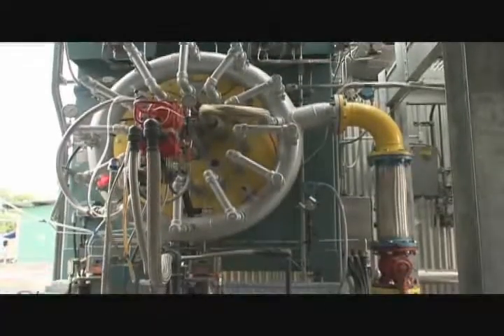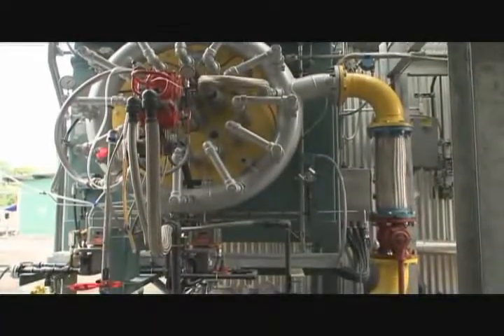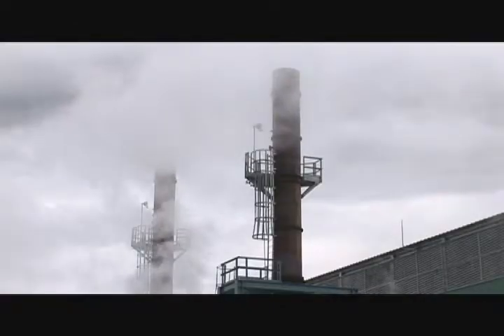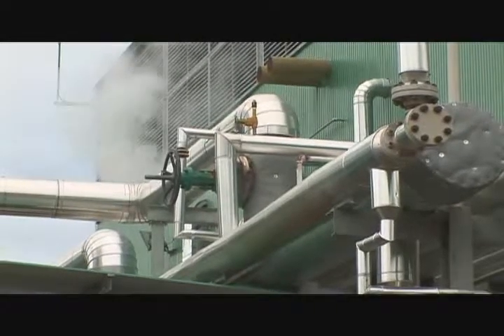The system is designed to burn the mixture of poor gas with a high CO2 content, and one part of rich gas, which comes from a vapor recuperation unit. This way, the boilers produce high-pressure and high-temperature water vapor, with which they fuel the turbines attached to the electric generators.